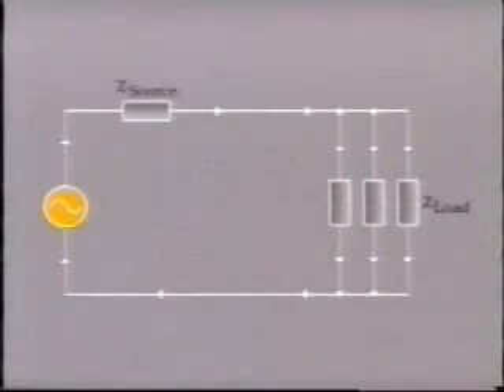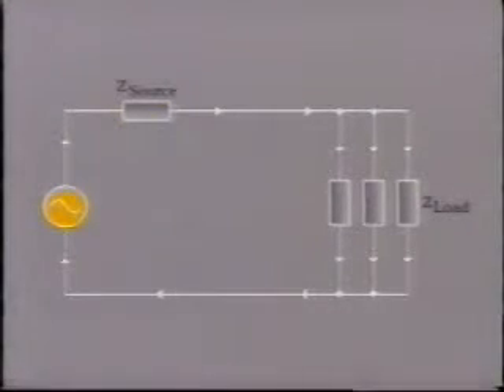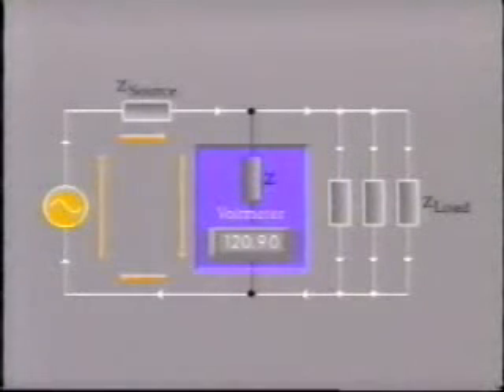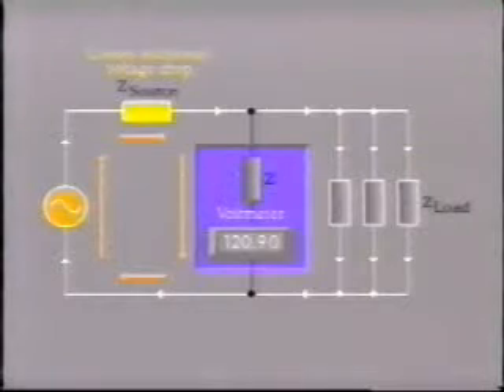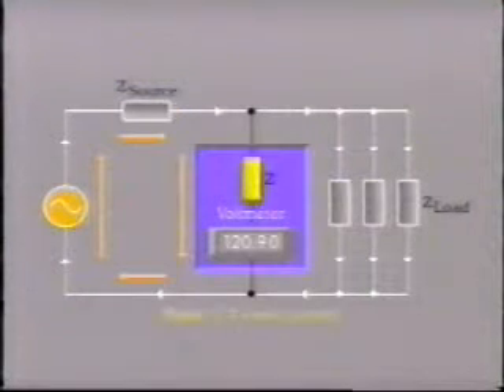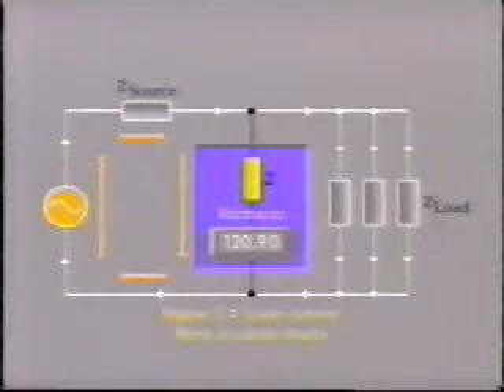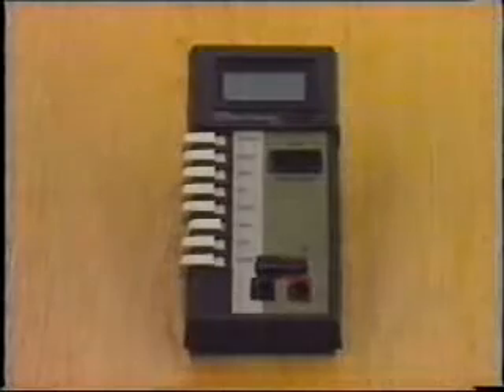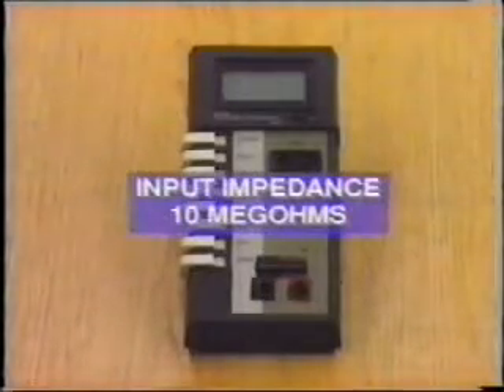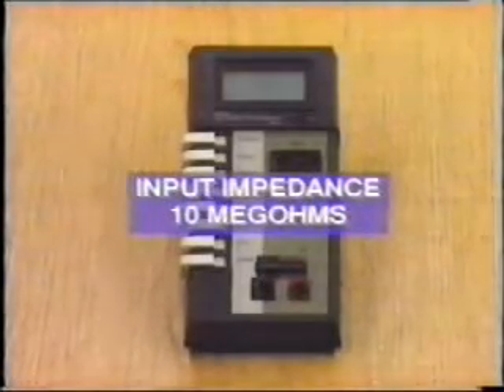When making voltage measurements, remember that the measured value can be affected by the impedance of the source itself. As soon as you connect the voltmeter to the circuit, additional current will flow, and this in turn will cause an additional voltage drop across the source impedance. Clearly, the higher the impedance of the voltmeter, the lower will be the additional current flow, and the more accurate will be the result. Typically, the DMM has an input impedance of 10 megohms, thus the loading effect is generally negligible.